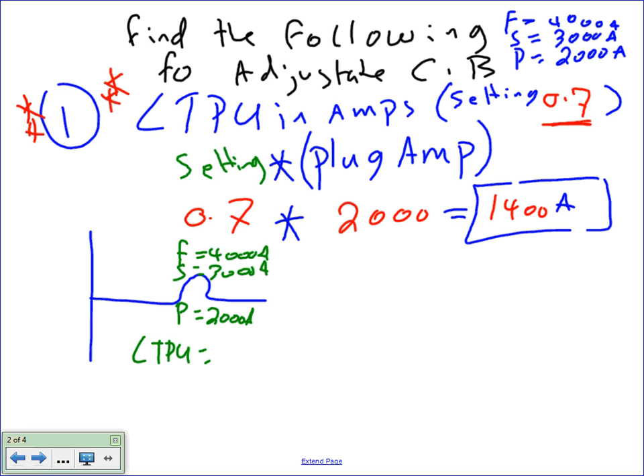I'm giving you the setting on the test. You're going to see a setting. You're going to see the frame size, 4,000, the sensor, the plug, all these sizes, and you're supposed to find the actual amp setting. Okay, now the question that you're going to see also on the test: I want you to size the feeder here. I want you to size this feeder. So tell me, you're going to have 4,000 amps for the circuit breaker. Which one are you going to be using to size the feeder?